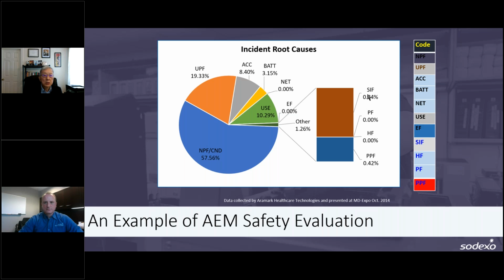Okay, so this is a good example why the safety and performance inspection needs to be performed after any repair, because something else may be hidden there. In this case, there was an oversight by the service person and it ultimately contributed to the demise of the patient. The patient died a few days later, not as a direct consequence of the ventilator failure, but the ventilator failure probably contributed to it.